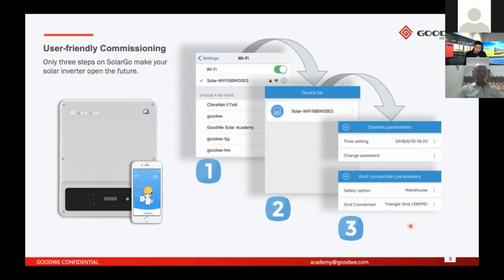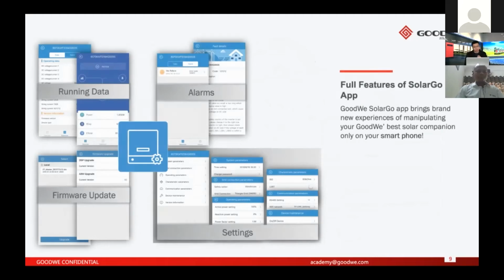There are only 3 steps for the installer to do the commissioning using SolarGo, plus some communication modules. The SolarGo app is not only for commissioning. It is also designed for local monitoring. It can provide 4 major pieces of information for you. The first one is the running data. Once you do the commissioning and connect your SolarGo app to the inverter, you can check the basic data at the DC side or AC side, and in the specific parameter page.